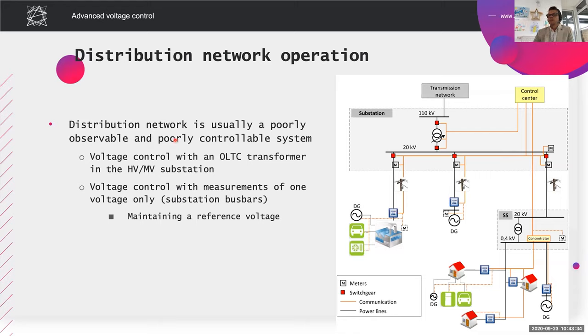And the second term: we have a poorly controllable system. It means that there are not many devices which can be controlled by the distribution system operator. In a traditional distribution network, the only controllable element is usually the transformer, the transformer which connects the high voltage side and the medium voltage side. This transformer is equipped with a tap changer, and with this tap changer, you're able to control the voltage in the whole distribution network. This is a very simple and straightforward control.